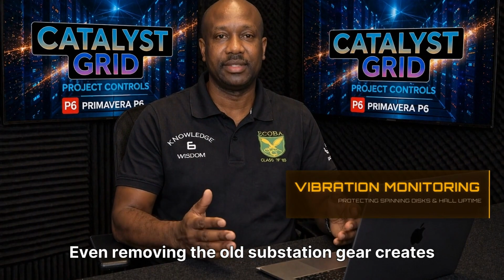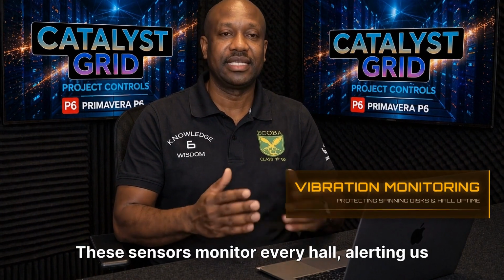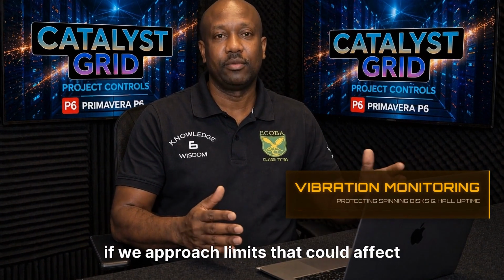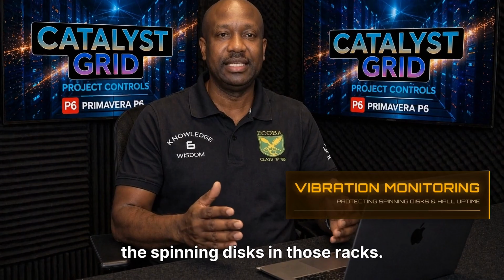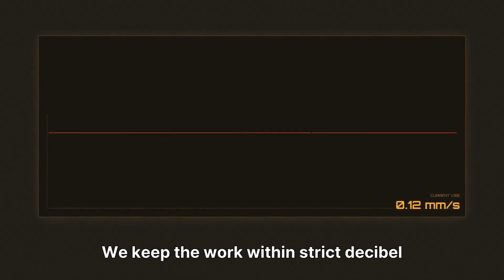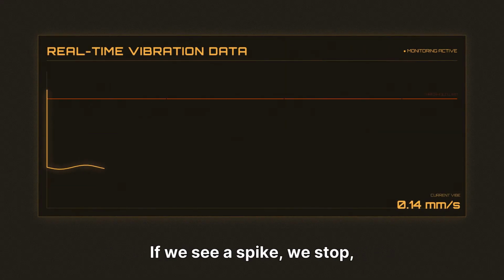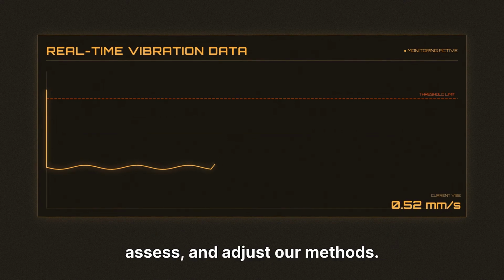Even removing the old substation gear creates vibration. These sensors monitor every hall, alerting us if we approach limits that could affect the spinning discs in those racks. We keep the work within strict decibel and vibration limits. If we see a spike, we stop, assess, and adjust our methods.